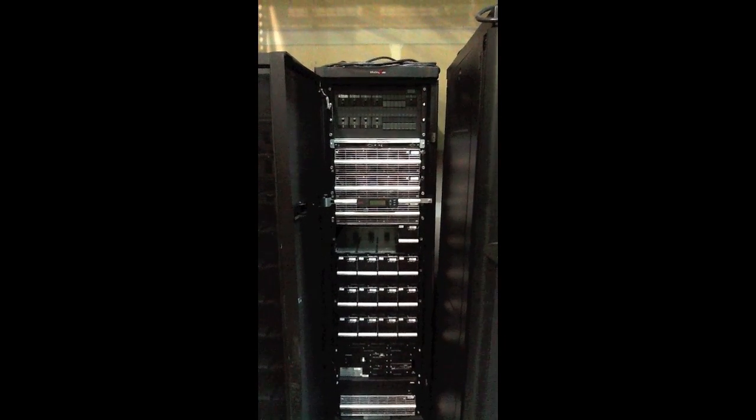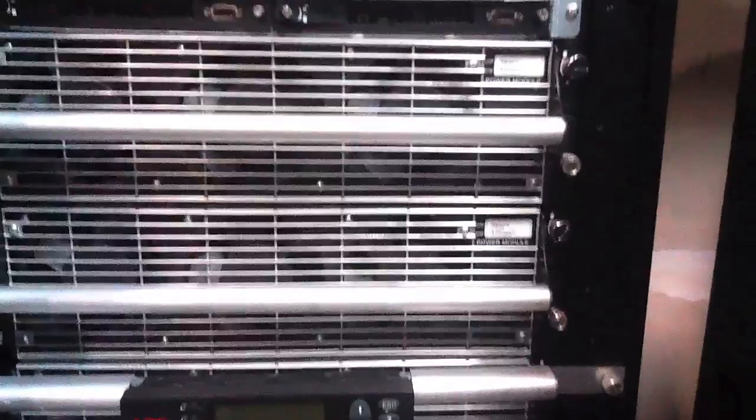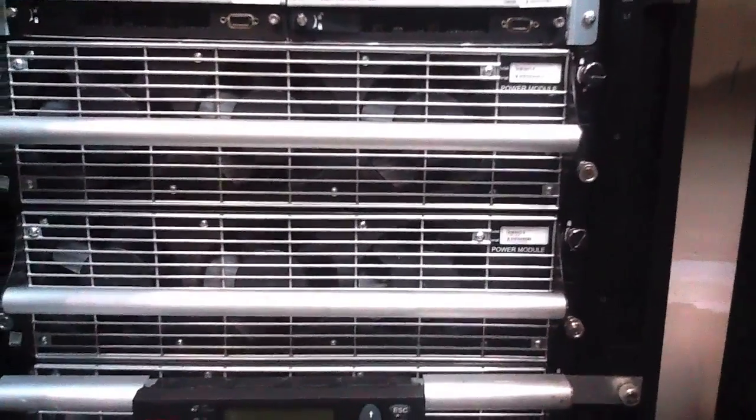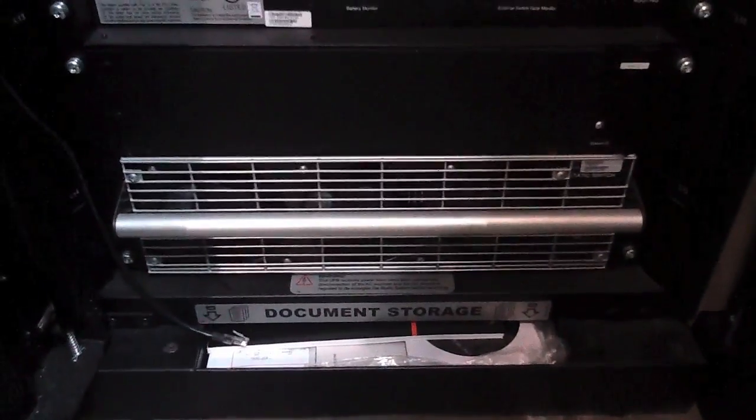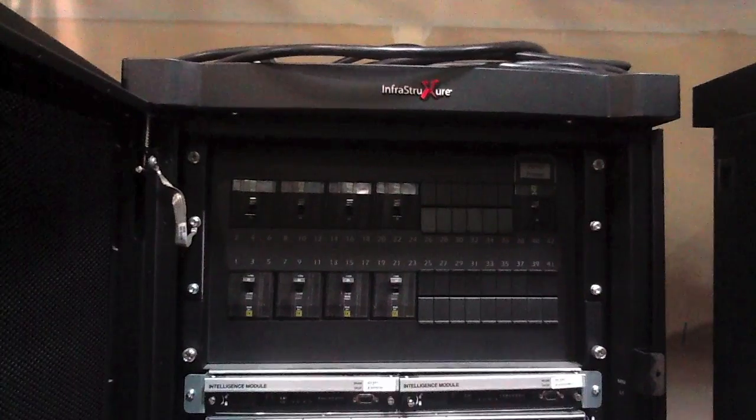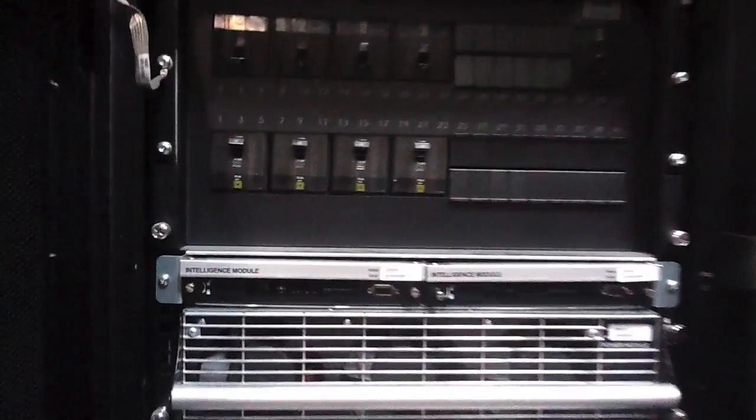All of the core modules, battery, power, and intelligence, as well as static switches, are run in and tested. If there is any deviation from specifications, the modules are replaced.